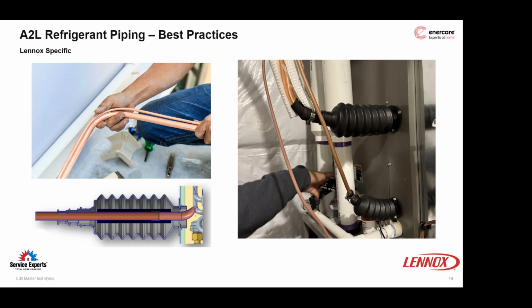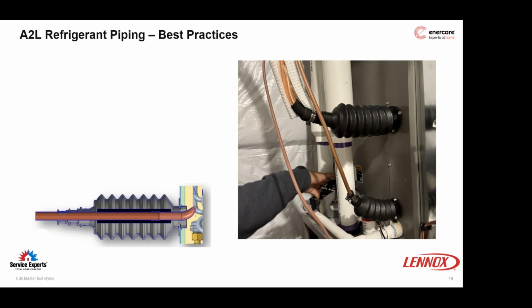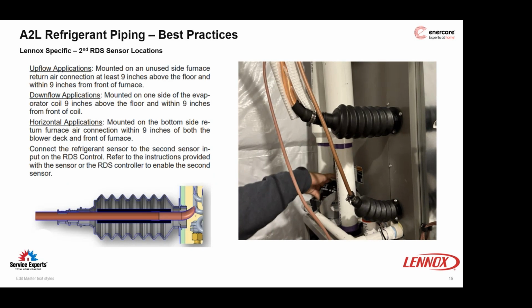Now, like I said, Goodman or Lennox has a different strategy. You can actually add a second sensor to one of the control boards. I don't know if you remember seeing the control board pictured, but Lennox, and ADP is the other coil manufacturer using that external RDS board. The one I showed you with the Lennox that was pictured, they're using the same one. So they both have 2 sensor mounts, so you can actually add an additional sensor outside of the coil.